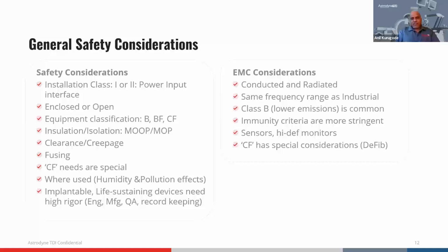Then the EMI considerations. Safety considerations are well defined and non-negotiable, and more or less the same rigor applies to EMI considerations, because the last thing you want is the medical system interfering with each other or causing problems to other equipment within the building. Worse, if you don't meet the local regulatory standards, you cannot go to market. So it's important to know where we stand when it comes to emissions.